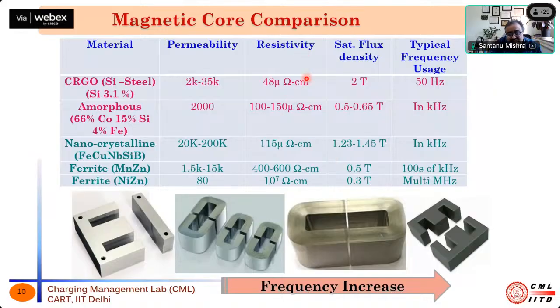You can see that in a CRGO core at 50 hertz, this is the resistivity. Think about the eddy current loss and its frequency relation - eddy current loss is directly proportional to the square of the frequency. So if I operate a 50 hertz transformer at 100 hertz, my eddy current loss becomes 4 times. If I do it at 100 kilohertz, you can imagine the amount of eddy current loss that will happen. Therefore, people use ferrite core which has much higher resistivity - a ferrite core doesn't even have any circulating eddy current, because of this type of resistivity.